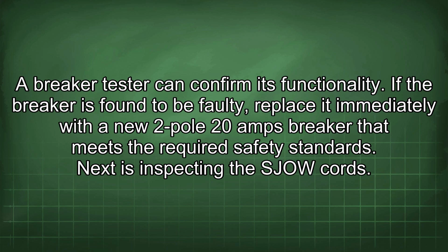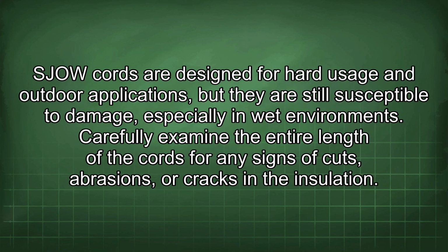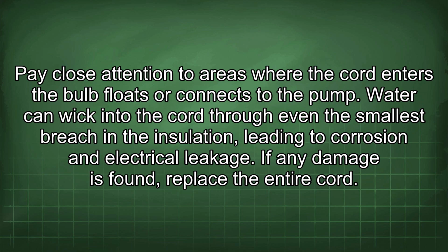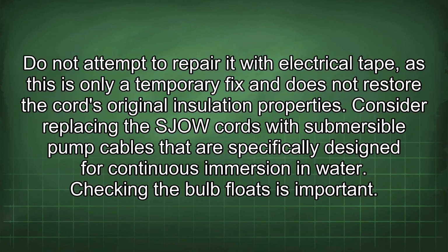If the breaker is found to be faulty, replace it immediately with a new 2-pole 20 amp breaker that meets the required safety standards. Next is inspecting the SJOW cords. SJOW cords are designed for hard usage and outdoor applications, but they are still susceptible to damage, especially in wet environments. Carefully examine the entire length of the cords for any signs of cuts, abrasions, or cracks in the insulation. Pay close attention to areas where the cord enters the bulb floats or connects to the pump. Water can wick into the cord through even the smallest breach in the insulation, leading to corrosion and electrical leakage. If any damage is found, replace the entire cord. Do not attempt to repair it with electrical tape, as this is only a temporary fix and does not restore the cord's original insulation properties.